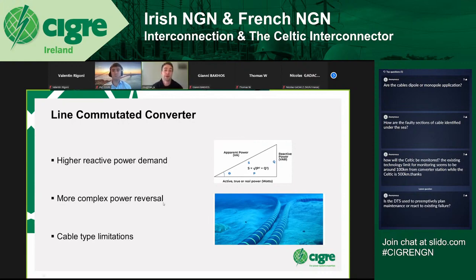Another reason is more complex power reversal. There are two cables joining both sides, a positive and a negative, and with LCC the current always flows in the same direction no matter which way the power flows. So to reverse the power flow, you need to reverse the polarity on the cable, changing it from positive to negative, and this brings stresses on the cable.